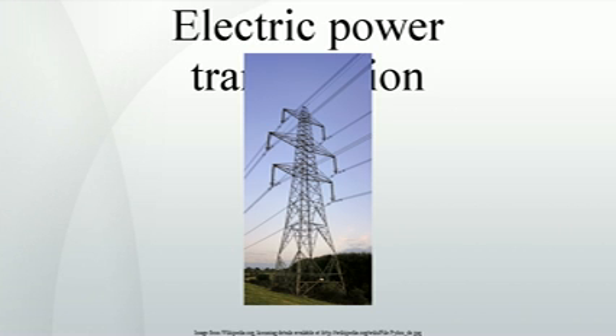Communications. Operators of long transmission lines require reliable communications for control of the power grid and, often, associated generation and distribution facilities. Fault-sensing protective relays at each end of the line must communicate to monitor the flow of power into and out of the protected line section so that faulted conductors or equipment can be quickly de-energized and the balance of the system restored. Protection of the transmission line from short circuits and other faults is usually so critical that common carrier telecommunications are insufficiently reliable, and in remote areas a common carrier may not be available.